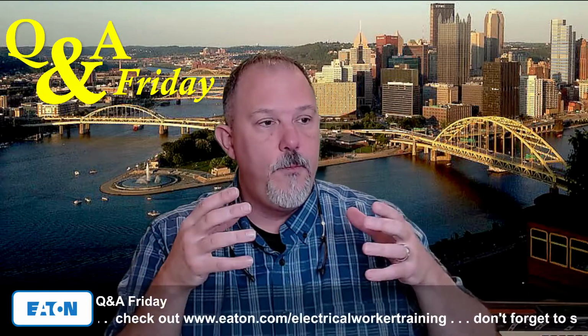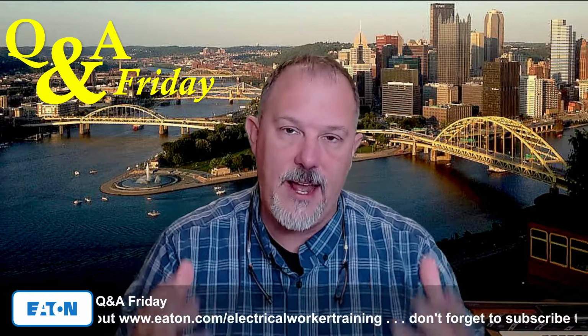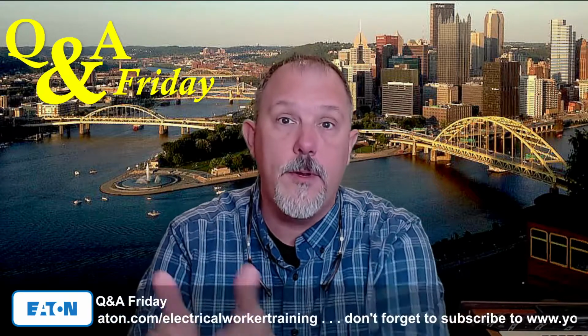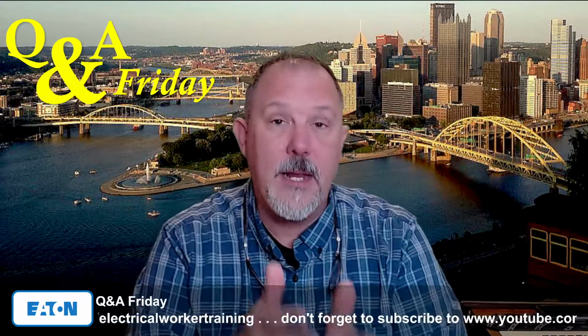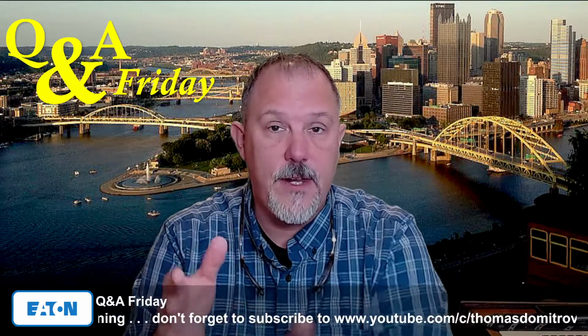And remember, they're going to be mounted either in an enclosure or in a panel board. And remember, a panel board's only that chassis. And then you're going to put the panel board in an enclosure, and the enclosure has to have a 3R rating or the appropriate rating. Depending upon the environment that you're going to put the circuit breaker in, you've got to put it in an enclosure.